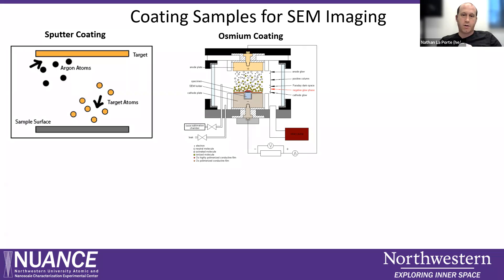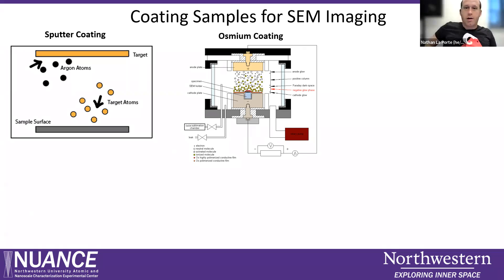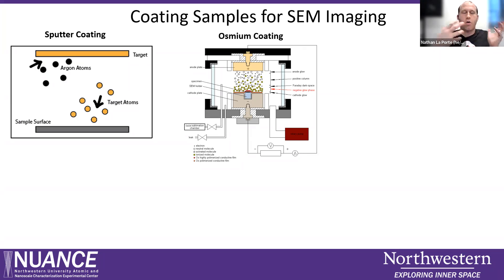The other coater that we have is the osmium coater. Essentially, the way it works is it sublimates osmium tetroxide from the sublimation chamber, which goes into the sample chamber. Then there's a plasma discharge that reduces that osmium tetroxide down to osmium zero, and that osmium zero then coats your sample and is conductive. What's cool about the osmium coater is that if you have a sample that's very porous or reticulated or has a lot of surface area, because the osmium tetroxide is coming in as a gas instead of as ballistic atoms like in the sputter coater, it can actually coat all the ins and outs of your sample and do a really good conformal job.